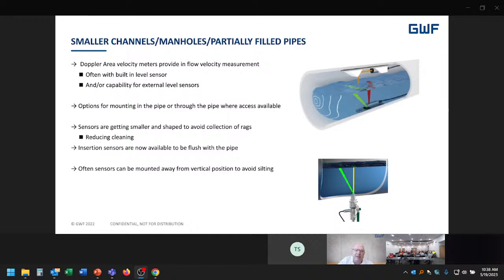However, the challenge with these types of sensors is obviously if it's wetted, if there's a potential for catching of rags around the sensor, you've got maybe a maintenance issue, at which point non-contact may be better. But if you're not looking at that, then these types of sensors can be installed in the bottom of a pipe or channel where access is available, or even underneath the channel, so an insertion type into the bottom of a pipe. That way, if there are any rags or otherwise, an insertion device is often designed to be flush with the surface of the pipe, which means that you won't capture those rags. You'll still be able to measure and reduce the needs for cleaning and maintenance.